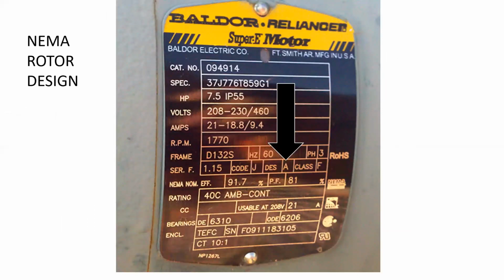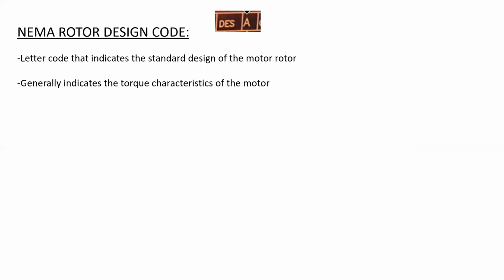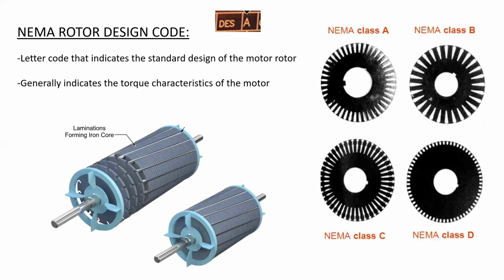NEMA rotor design. This motor has a design A. The NEMA rotor design code is a letter code that indicates the standard design of the motor's rotor. This generally also provides some insight into the torque characteristics that the motor will exhibit. There are 4 different NEMA classifications or designs, and what we're referring to here is how the bars have been shaped and what the iron core laminations look like if we were to remove one. Each one is shaped a little bit differently, and because of that, it's going to have different characteristics when it comes to how much starting torque and running torque the motor has. You don't have to memorize the shapes of these, but we will look at them in more depth in a later presentation.